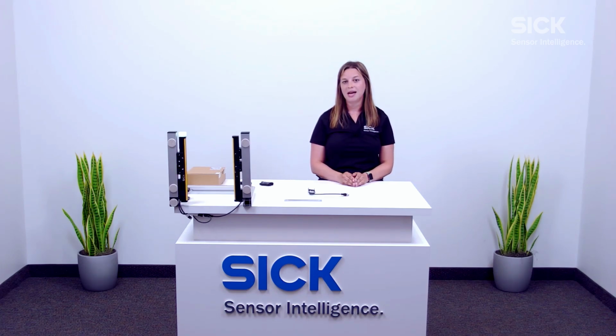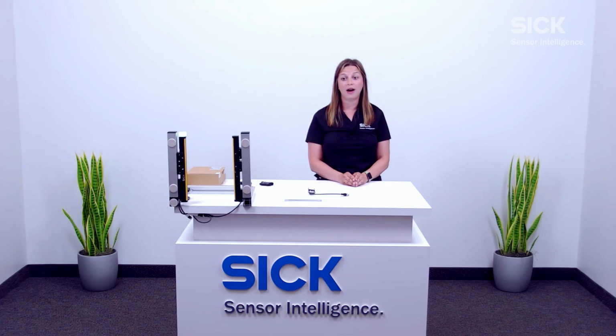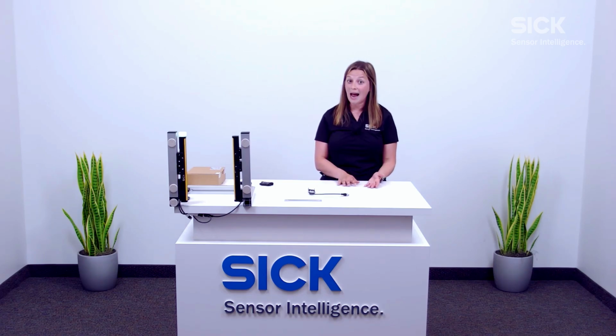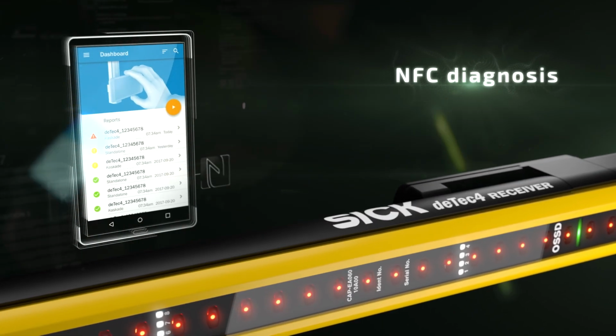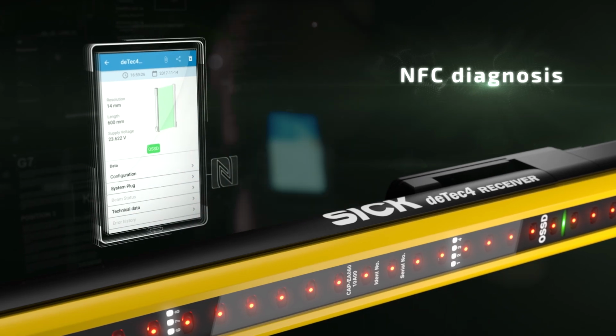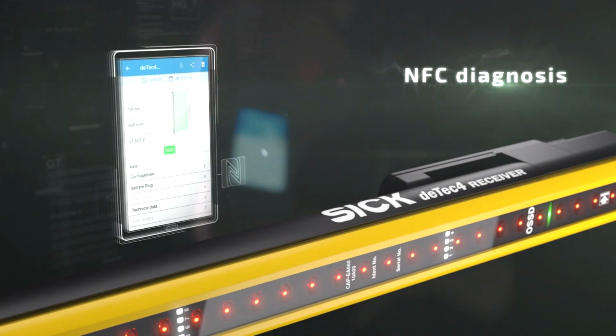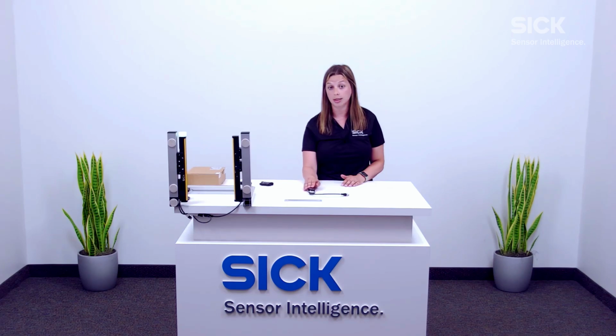When we configure this, we actually have the option to support 3 different detection ranges or detection widths between our sender and receivers. The first one is low, which is between 0.15 meters up to 5 meters. Then we have our mid-range that supports between 1 and 10 meters, and then our high range that supports between 2 and 20 meters. You can easily program this using a feature that we have called our SICK Safety Assistant app. Within this, it will show you how to set the dip switches on the back of our light curtain system plug. You can set it for your specific range.